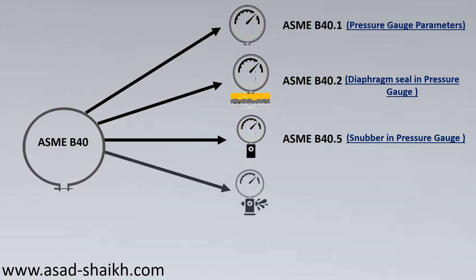The next part is ASME B40.6, which covers the gauge saver — also referred to as a pressure limiting valve. This specifically deals with protecting the pressure gauge in high-pressure applications. For example, if a pressure gauge has a maximum pressure of 50 psig but the design pressure is 150 or 500 psig, you would use a gauge saver. If pressure goes beyond a set limit, say 80 psig, the gauge saver activates and diverts pressure away from the gauge.